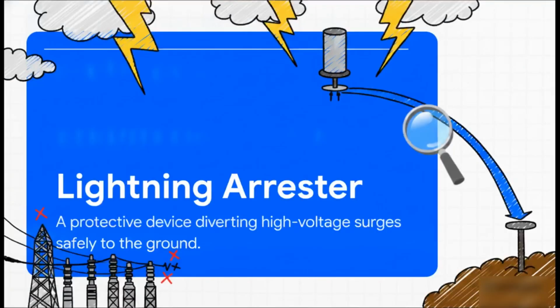Let's zoom in on a specific substation and look at the actual equipment doing the heavy lifting. The very first piece of equipment that incoming power encounters is the lightning arrestor. You can kind of think of this as the grid's bouncer. If lightning strikes a transmission line nearby, or if a switching surge causes a huge unexpected voltage spike, the arrestor instantly diverts that dangerous excess voltage safely straight into the ground. This ensures the rest of the extremely expensive equipment doesn't just get completely fried.